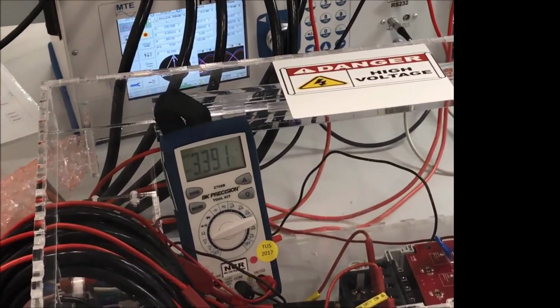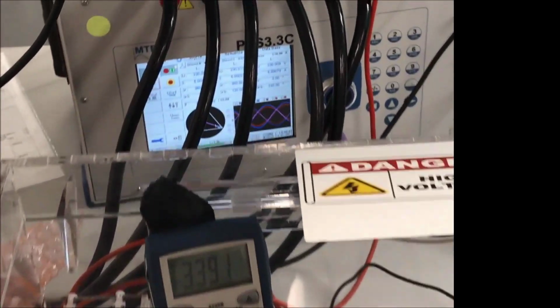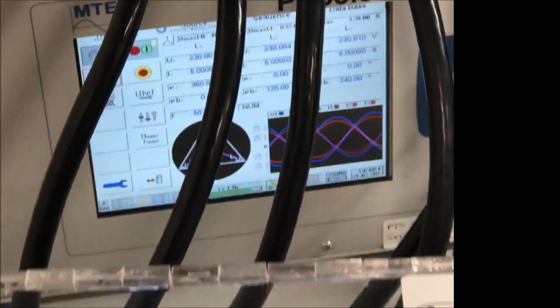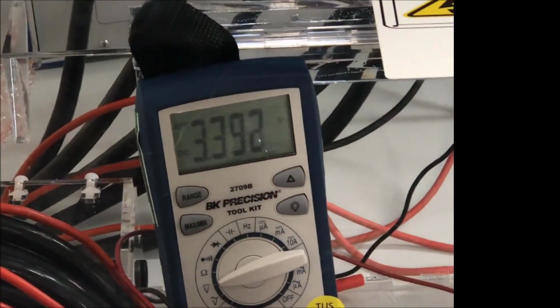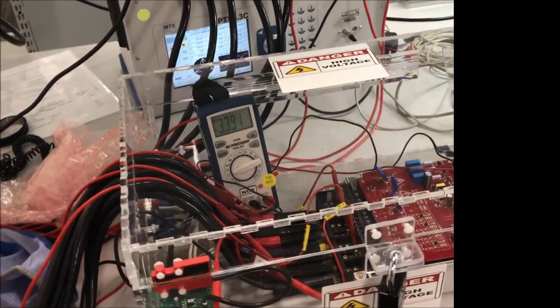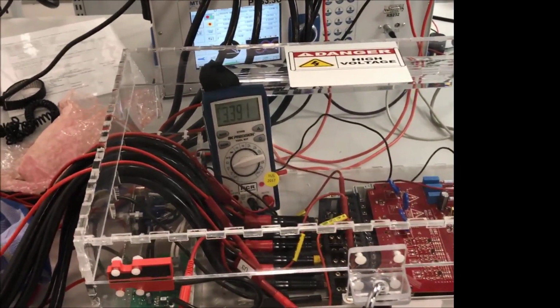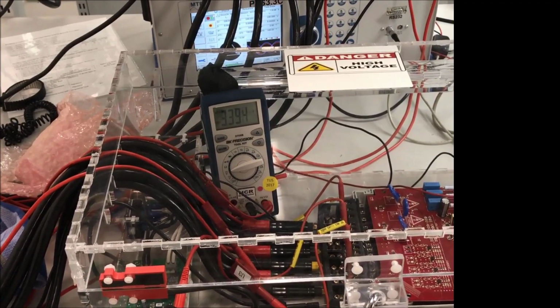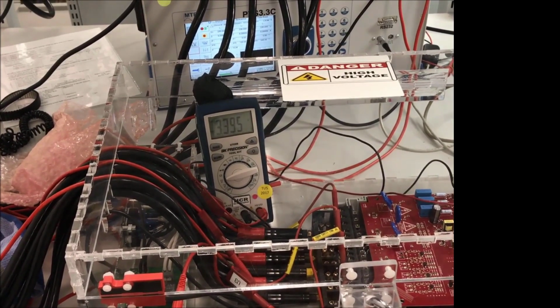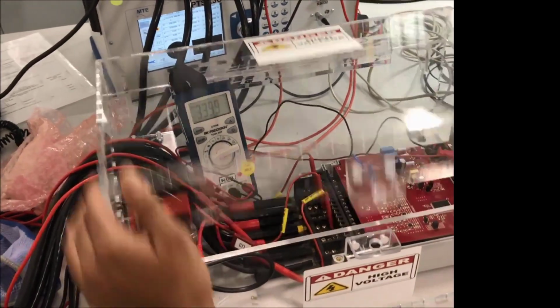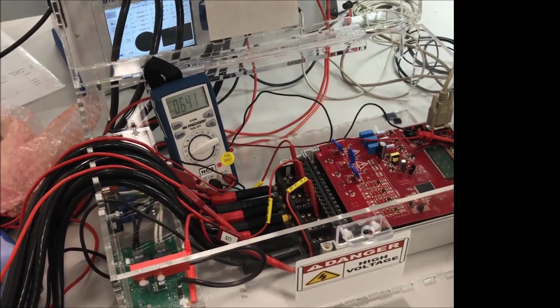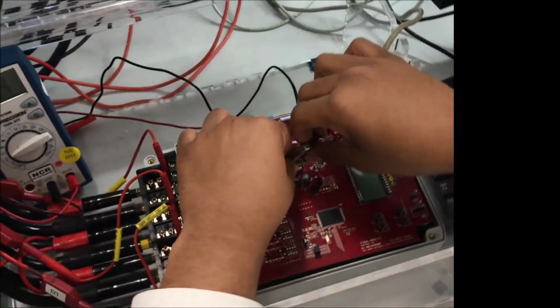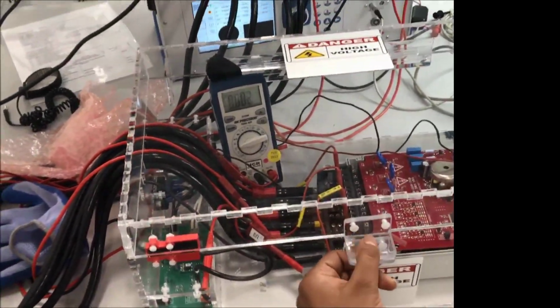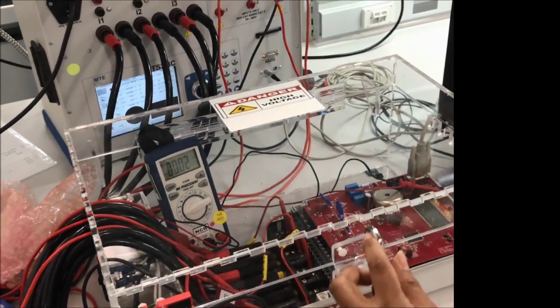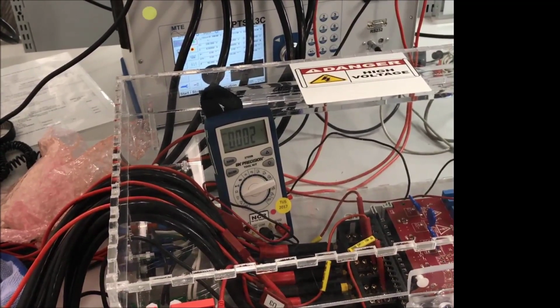Here we see that it is 3.391 volts when each phase has 230 volts applied to it. Now we'll see what the reading is when we apply a powerful magnet to the power supply transformer. For this test, for safety reasons, we place a physically smaller magnet than one used for e-meters, but we place it closer to the transformer in order to better simulate the actual conditions of when someone performs magnetic tampering. Here we place the magnet on top of the ferrite core transformer. So we close the system up and apply the same 230 volts input from our source generator.